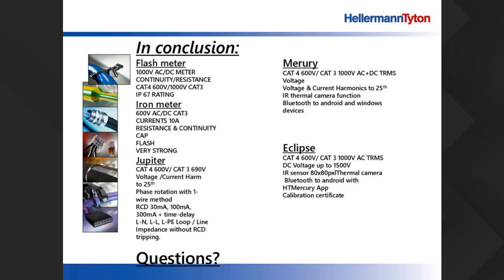The Mercury meter is our first of 2 meters that's got a built-in thermal camera. So it's also a Cat4 600 volt TRMS multimeter. It measures voltage and current harmonics. It does the thermal function, and it works. It allows you to connect via Bluetooth to Android phones or Windows devices.